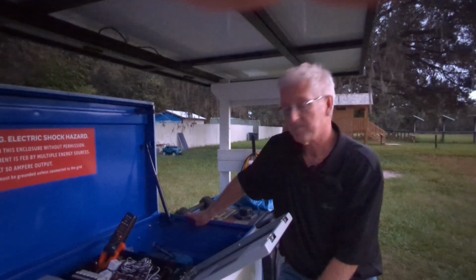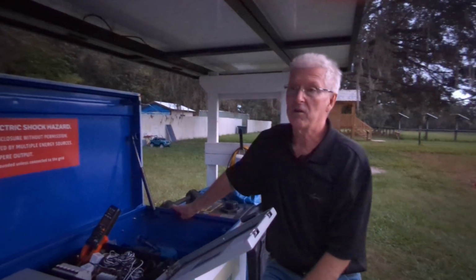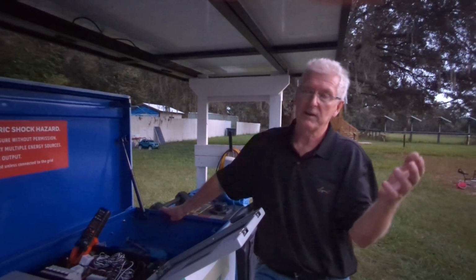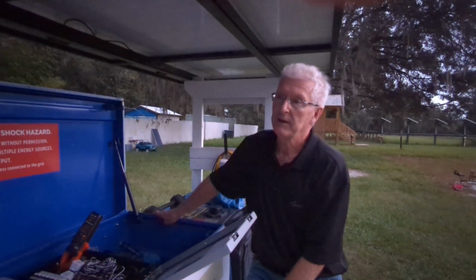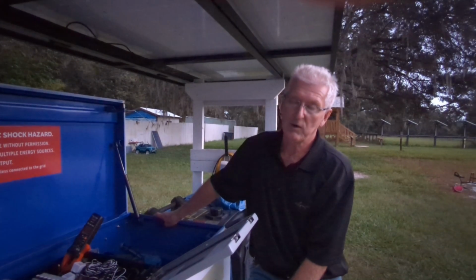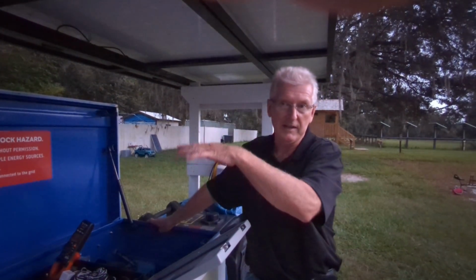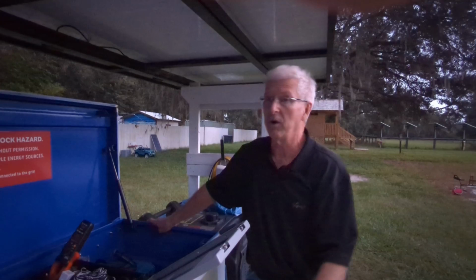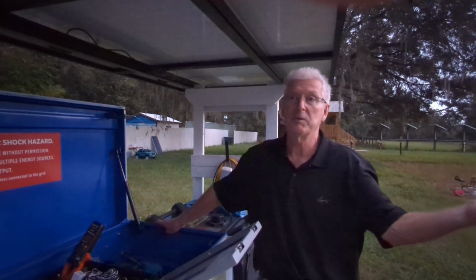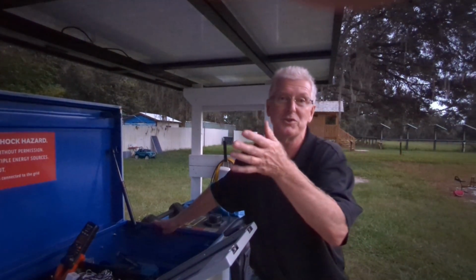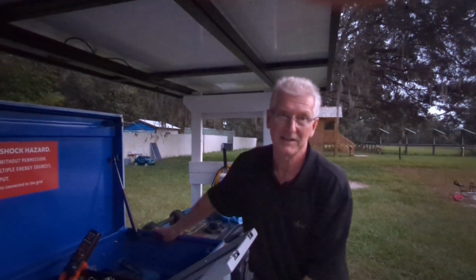So the advantage of the auto transformer would be nil at this point. Going back to the auto transformer, yeah, I got off track. So going back to the auto transformer, what it's going to do is if you want to pull 3.5 on a leg that can only handle 2.5, and 1 on the other leg, the sum total would be 4.5. It's going to balance those two at 2.25 on each leg.